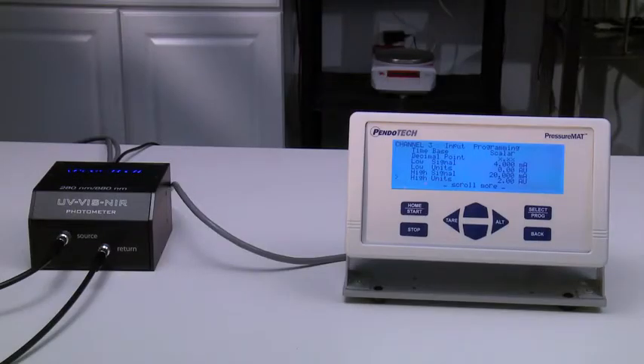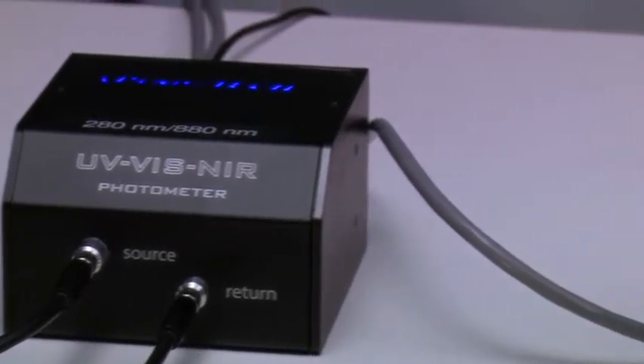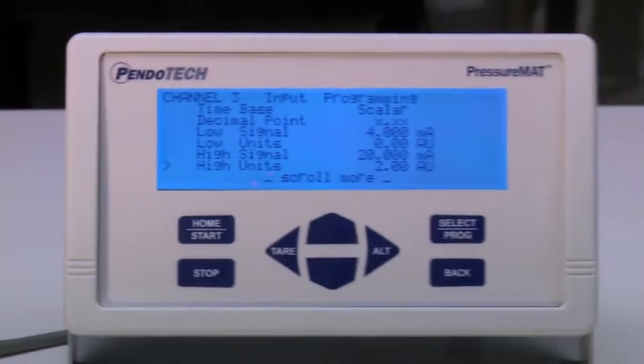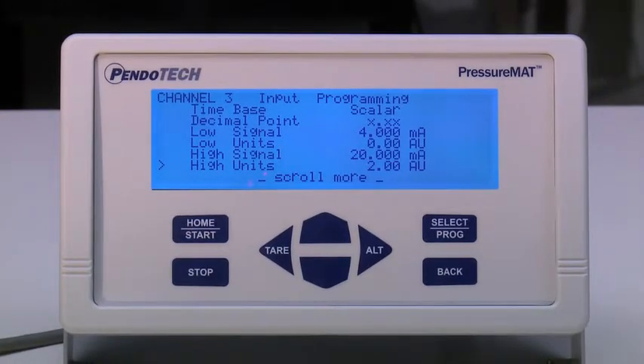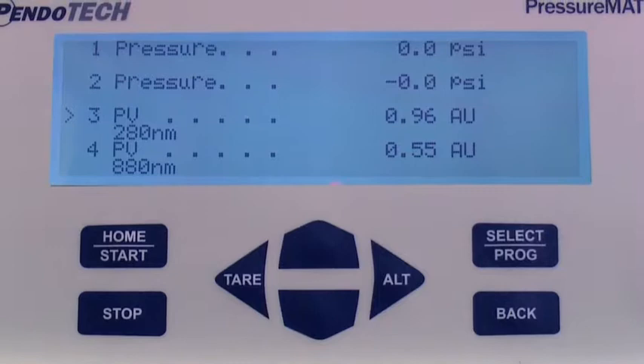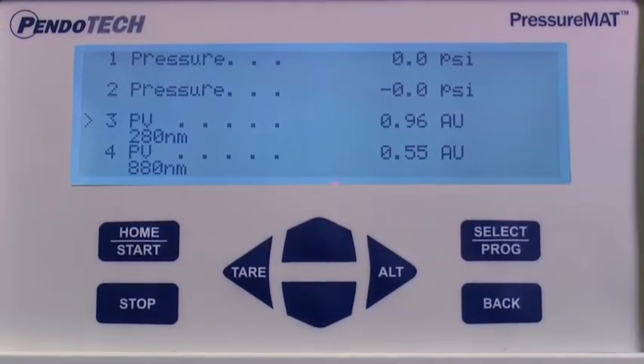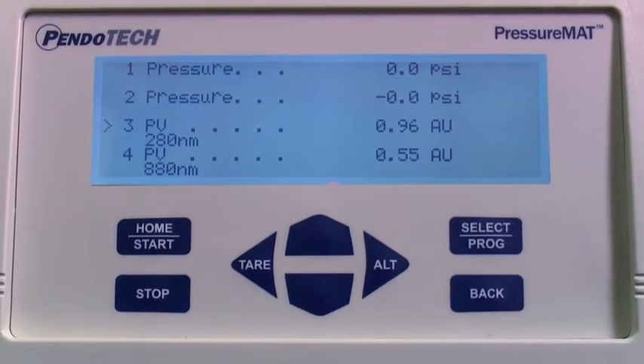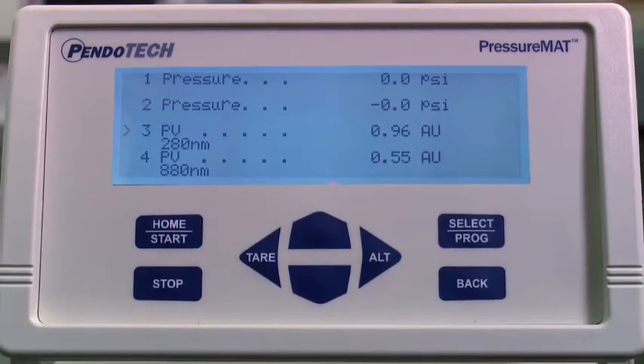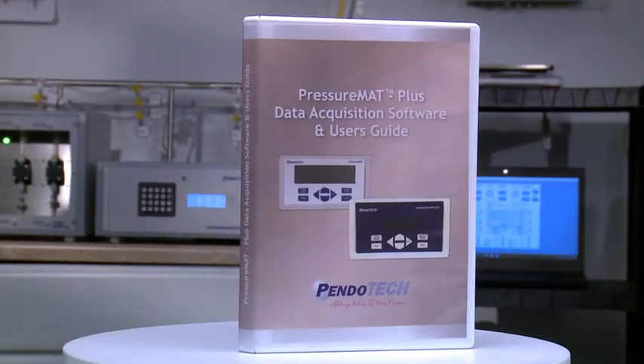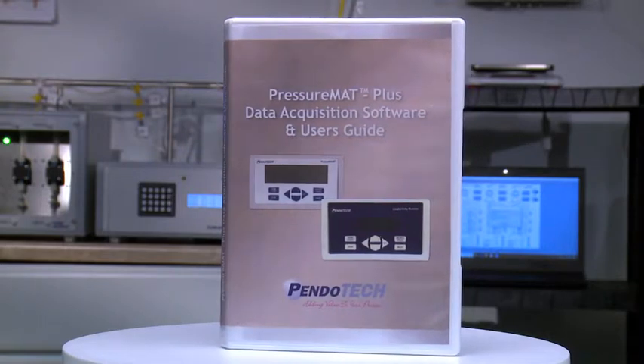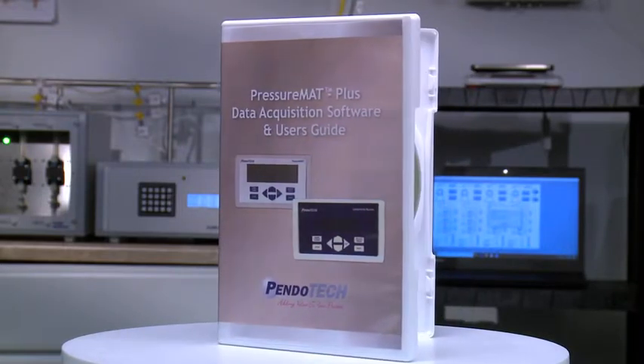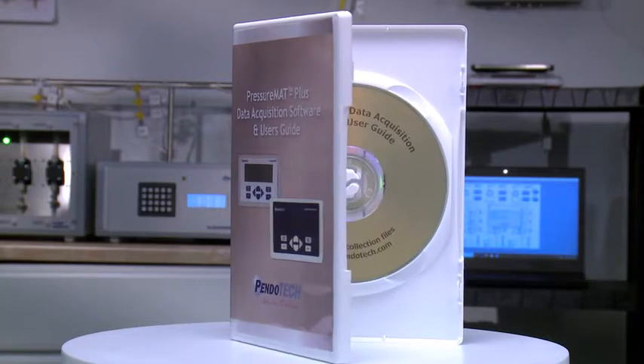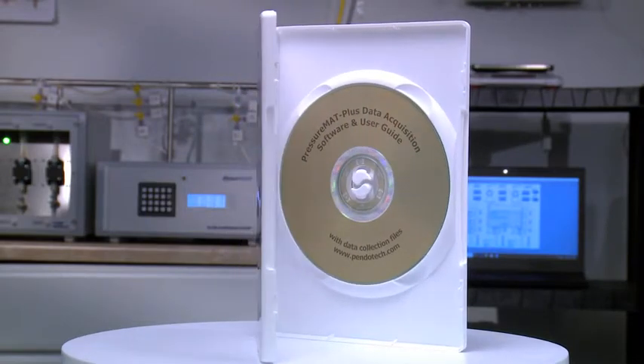The analog input captures the reading from the photometer output, and the user sets the 4 to 20 milliamp range of the device to 0 and 2 and sets the units to AUs. The absorbance reading now will appear on the receiving device, labeled with proper units of measure, and can be viewed and logged. PendoTECH offers the PMAT Plus GUI software package that can be used to trend the data real-time and log the data to file for future use.